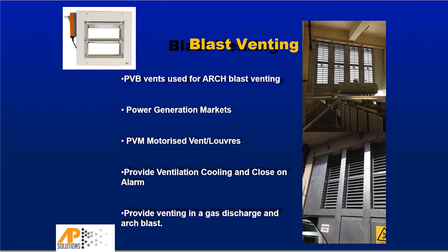This means that the pressure vent can be motored open in the open position all the time in normal application to allow airflow. But on a fire signal, the motor will close the pressure vent, and then the pressure vent linkage will allow the blades to open freely as a pressure vent.